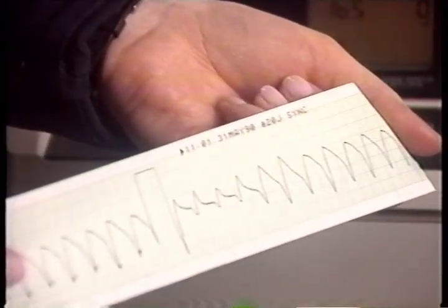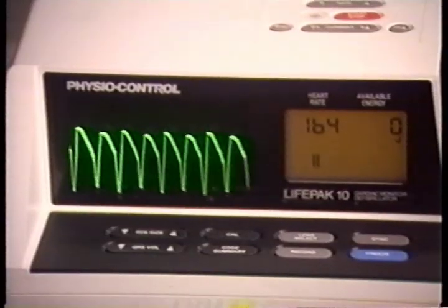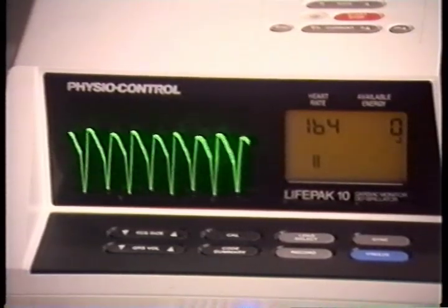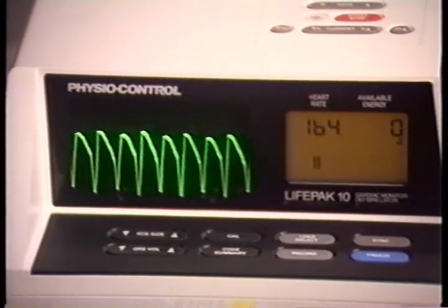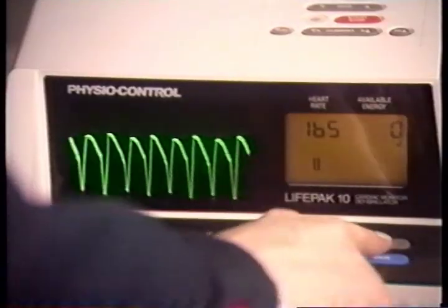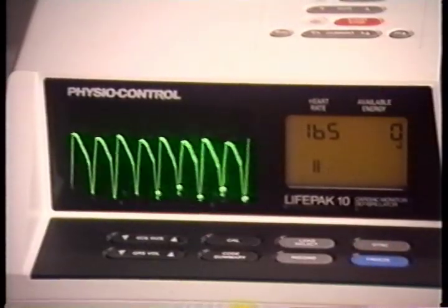If the recorder is running, it will annotate time, date, energy selected, and sync after discharge. Immediately following the discharge, the defibrillator automatically reverts to the asynchronous defibrillation mode. If a second synchronized shock is needed, push the sync button again to activate the sync mode.